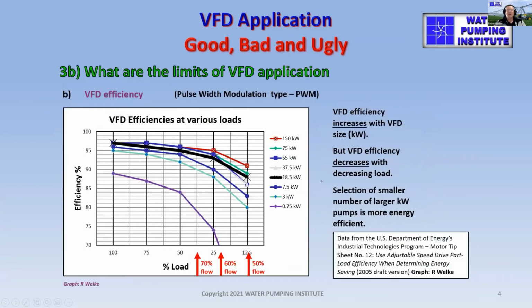It's also known as a frequency converter because it changes the motor speed by varying the alternating current frequency, as Roger's pointed out. There's an inherent inefficiency in VFDs, and this data is taken from the US Department of Energy's Industrial Technologies program, and I've graphed the table. So you can see a typical 18.5 kilowatts, the thick black line, at a 50% loading, that VFD is only 95%. So you put in 100 kilowatts, you'll get out 95. And if you go for 150 kilowatts, the answer is not much different.